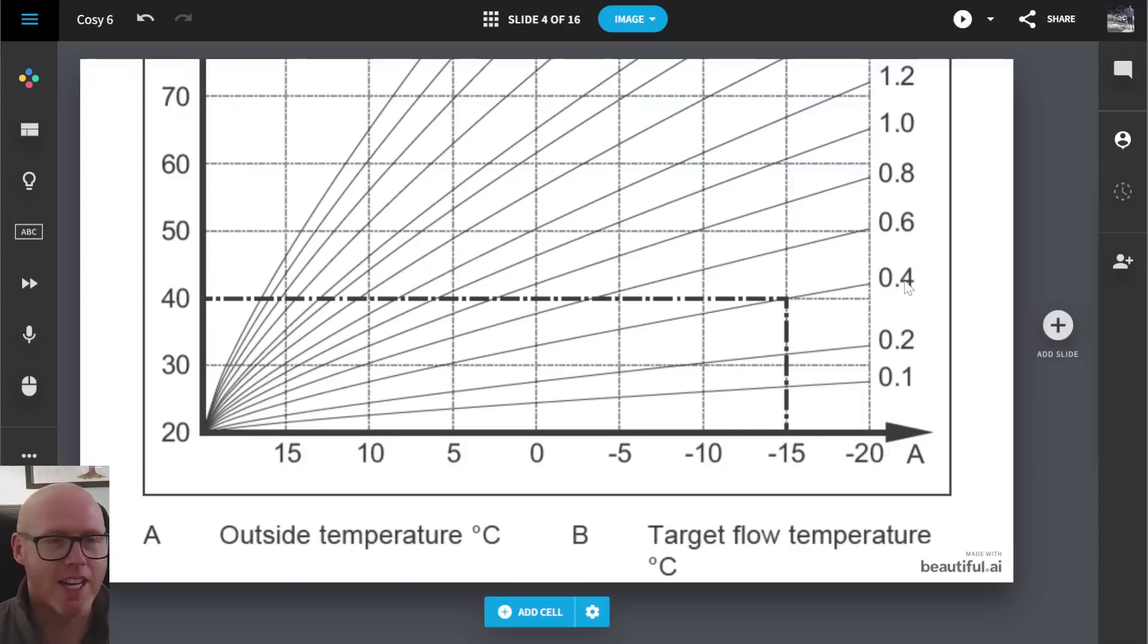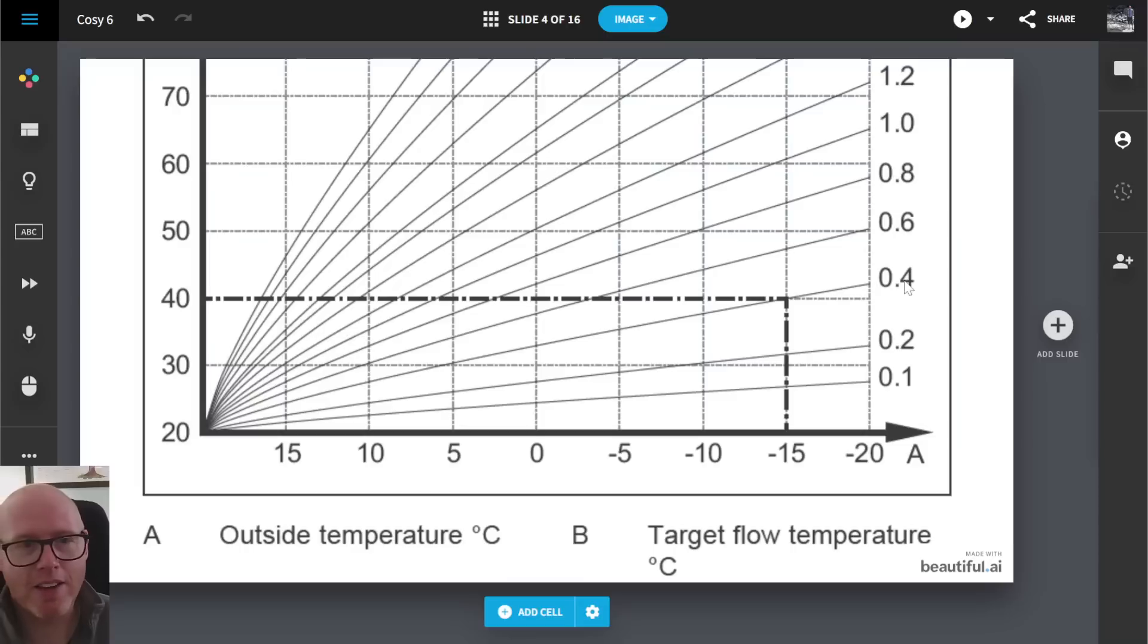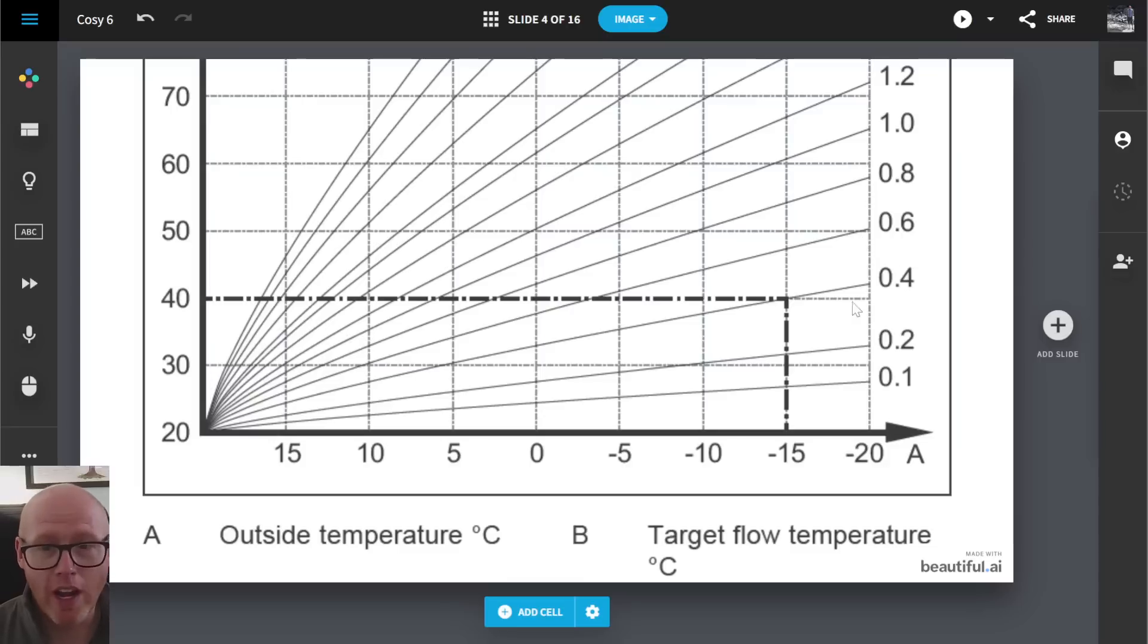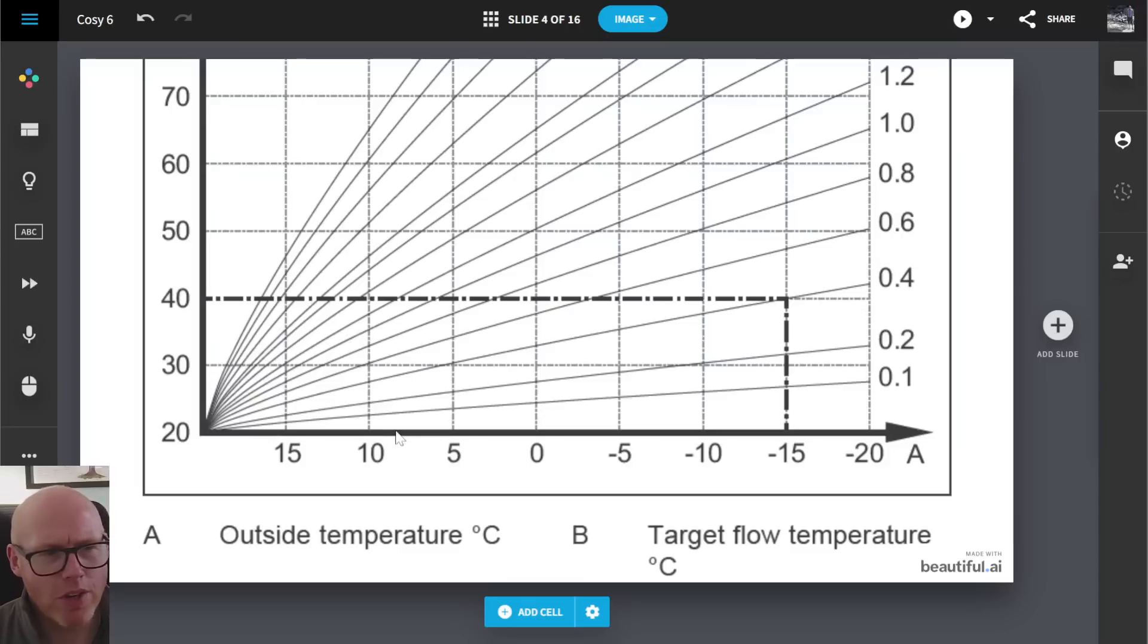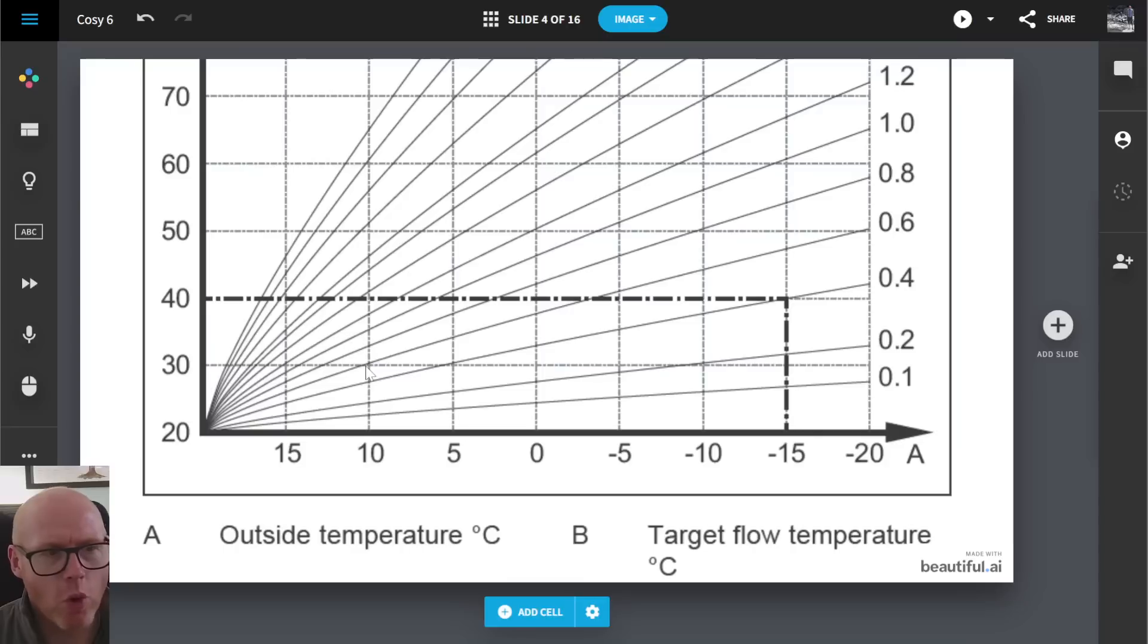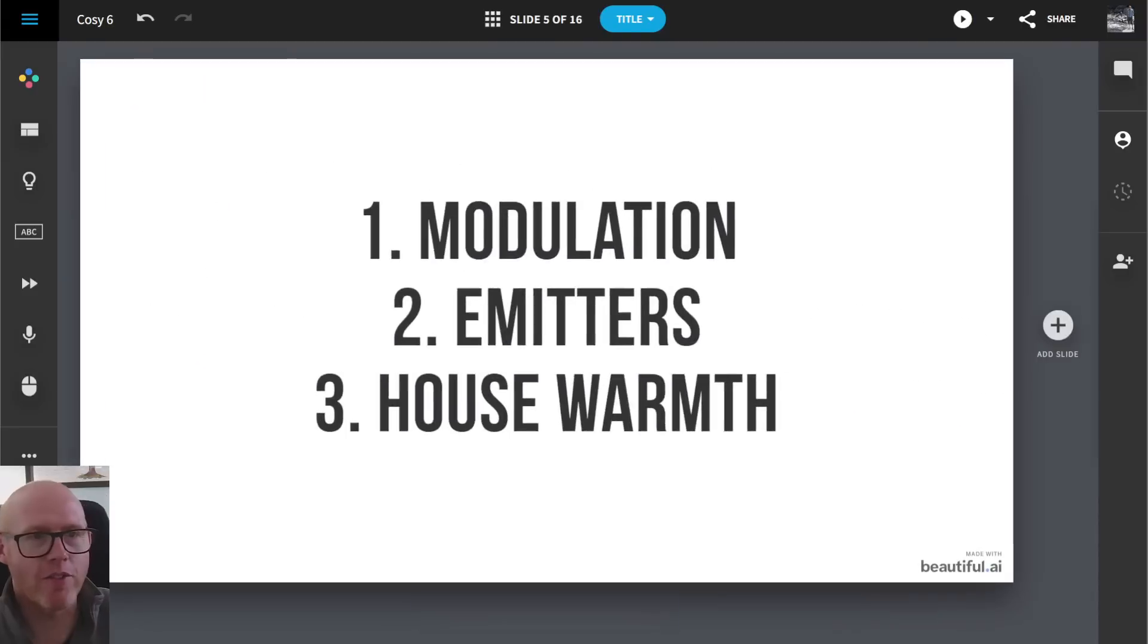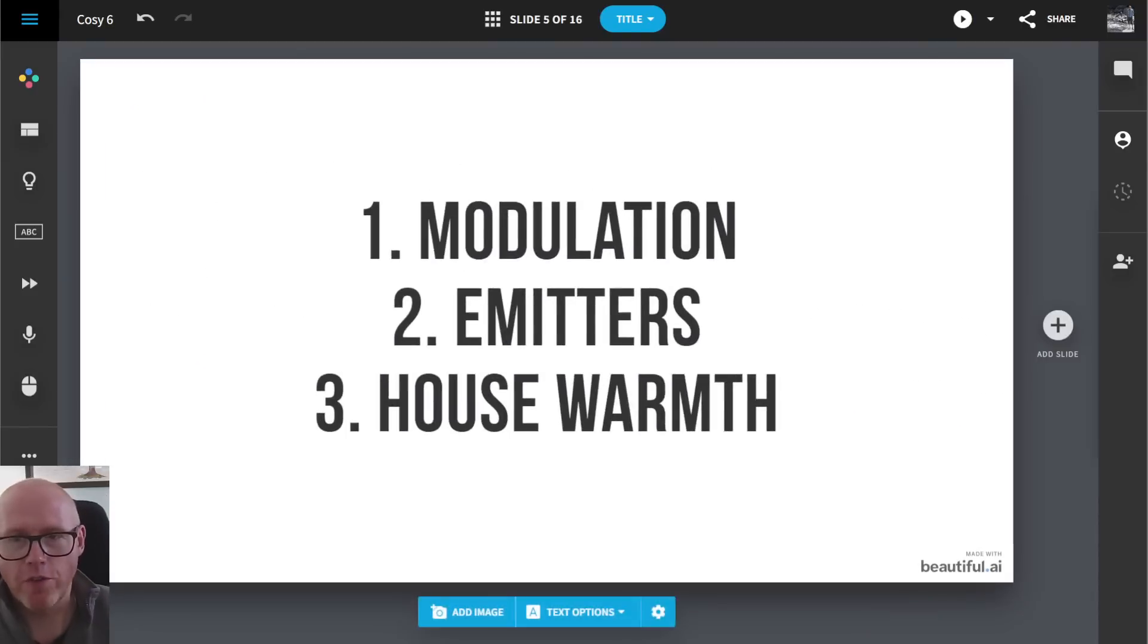But typically most of the Vaillant heat pumps operate 0.6, 0.7, that sort of area. So it's quite a low heat curve that he set that. And also it was interesting that he said it was 30 when it was warm and 35 when it was cold, which is quite a shallow heat curve compared to what the Vaillants operate at. Anyway, enough of this comparison.